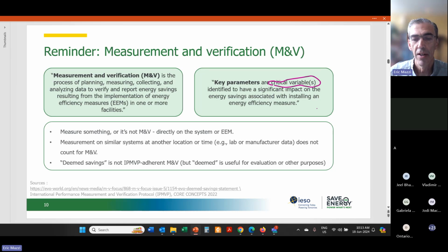The best definition I keep in my head is, if that variable changes, then your energy consumption changes. So if it's an HVAC system in a building, any significant change in outdoor air temperature will change the consumption of the heating, cooling, maybe ventilation systems. In a lot of industrial processes, sometimes outdoor air temperature is not a key driver. Electric or fuel consumption in an industrial process might be very insensitive or independent of outdoor air temperature. So that's just one simple example of a key parameter: outdoor air temperature. Sometimes it is a key driver of the process, sometimes not necessarily.